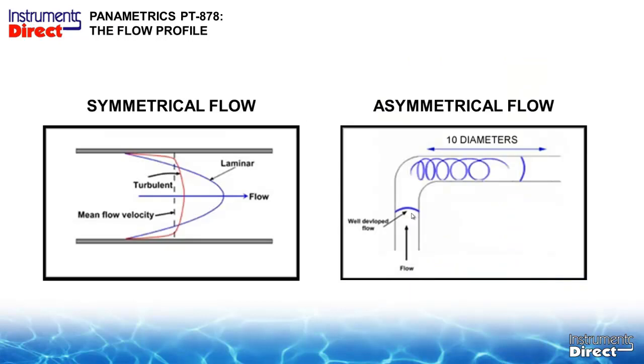Now, all technologies require some straight run of pipe, and this is no different. For optimum performance, what you need on the left hand side is called the symmetrical flow profile. A symmetrical flow profile is basically where the flow is the fastest in the center and the slowest near the pipe wall. And this scenario traditionally exists in applications where you have your 10 to 15 pipe diameters. So say I had an elbow to the left here, I'd have 10 pipe diameters, I'd put my sensor here, and then I'd have another 5 diameters to the next elbow. In a symmetrical flow profile, I said the flow is at the fastest in the center, slowest at the pipe wall. These different shapes are referred to as Reynolds numbers.